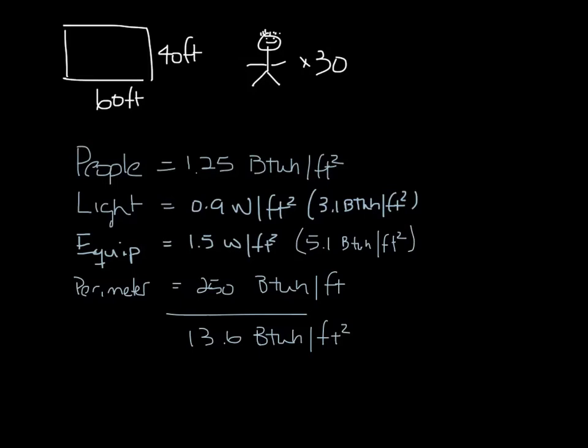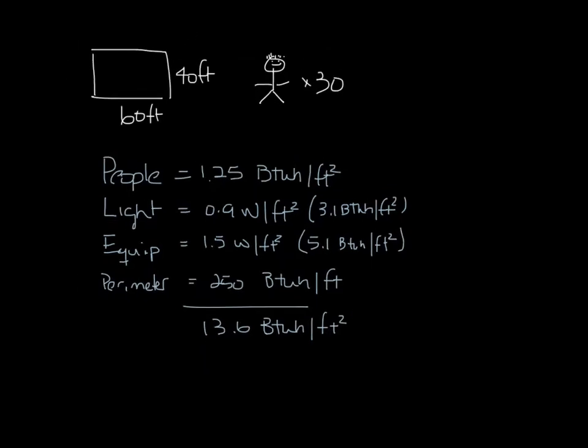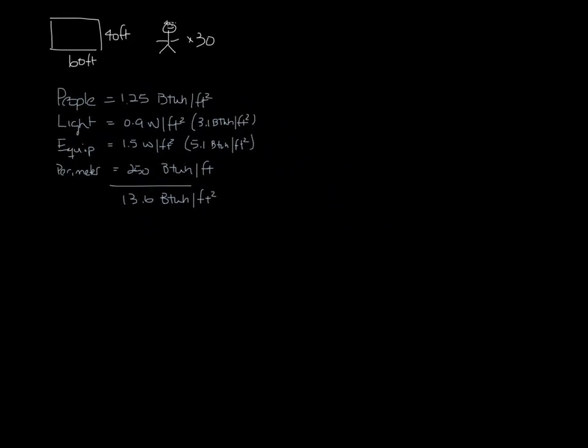So now let's calculate the sensible and latent loads. The latent load is from the 30 people, and per ASHRAE, there are 200 BTU per person, which gives us 6,000 BTU of latent load.